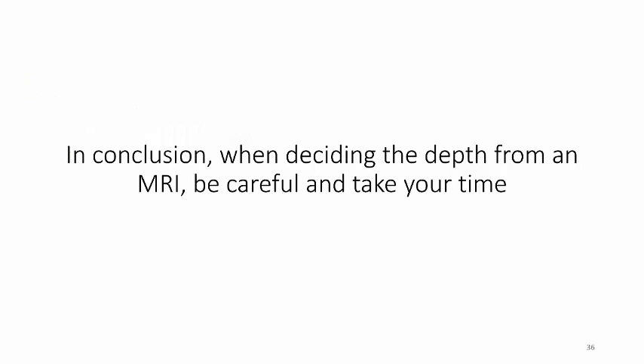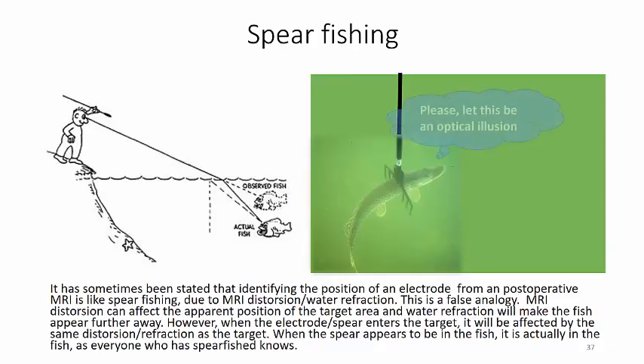Concerning MRI, I would also like to mention that it has sometimes been stated that identifying the position of an electrode from a postoperative MRI is like spearfishing due to MRI distortion and water refraction. This is a false analogy. MRI distortion can affect the apparent position of the target area and water refraction will do the same with the fish. However, when the electrode or spear enters the target, it will be affected by the same distortion and refraction as the target. When the spear appears to be in the fish, it is actually in the fish, as everyone who has spearfished knows — and the same is true regarding the electrode.